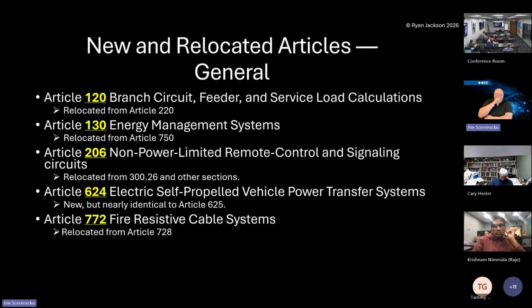interesting. The reason why 2-hour fire resistive cable systems has become very popular is that one of the major code changes that comes about in Article 230 is, for how many years have we been considering 2 inches of concrete to make it 2-hour rated, right? Or outside the building or all that other stuff. That actually changes, because they came to find out that the 2 hours just wasn't holding up. It was only standing up to about 45 minutes. And so after they did some heavy testing on the systems, it now has to be encased in 5 inches of concrete. So that's going to make 2-hour resistive cable very popular.